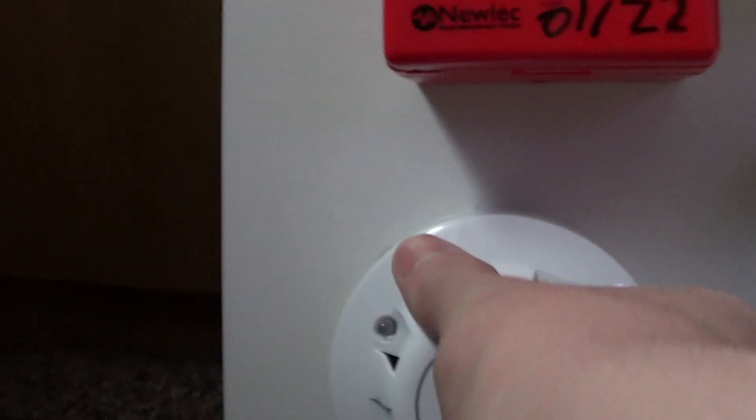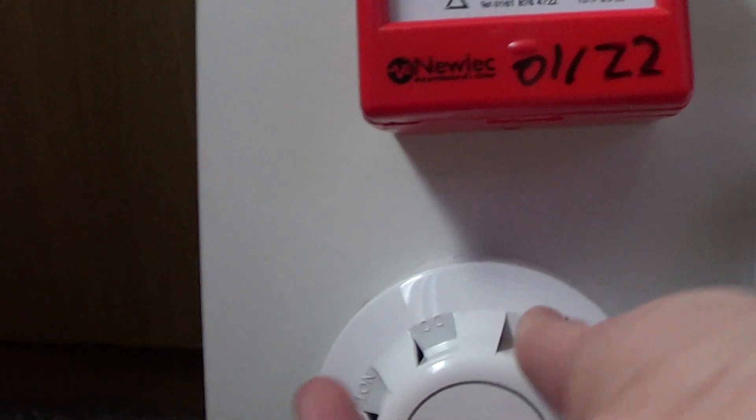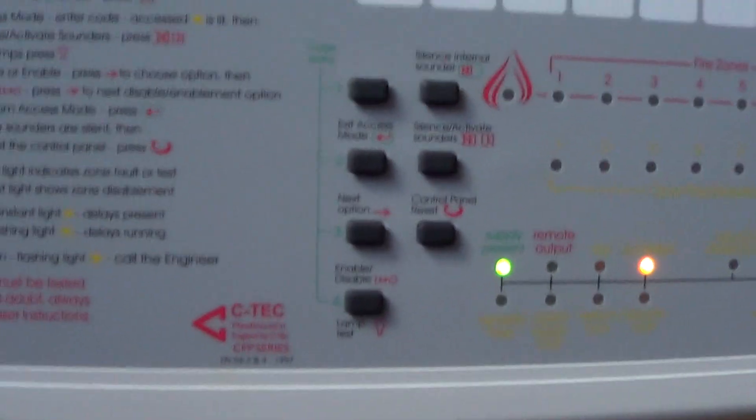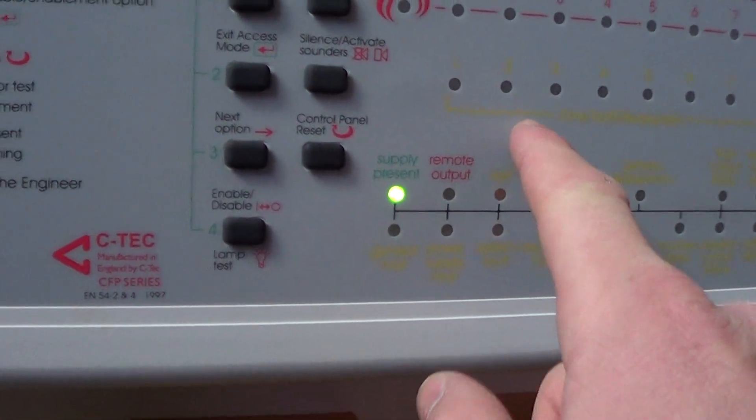Now put this back on its base. I have to be careful with this detector because I've taken it apart. I'll now reset that. Now that's back on, the fault should clear on zone two. You see it's cleared.